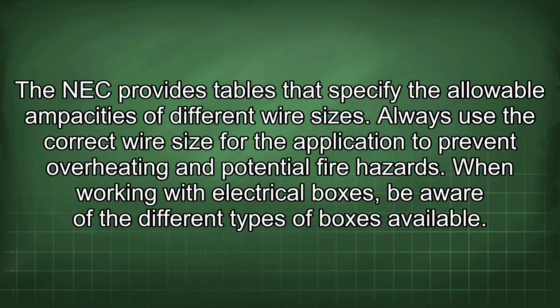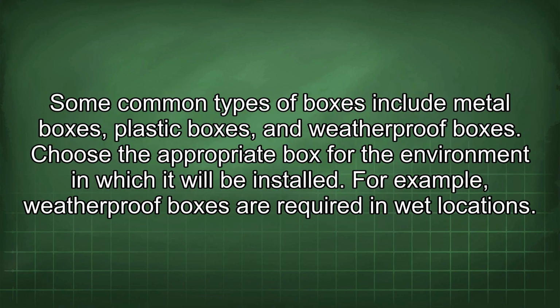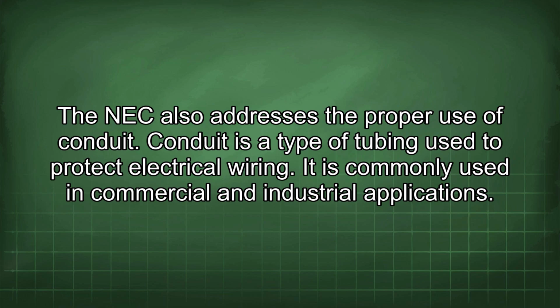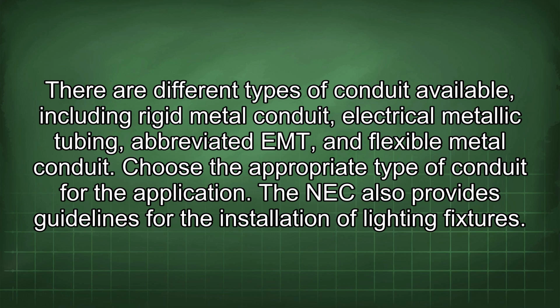When working with electrical boxes, be aware of the different types of boxes available. Some common types of boxes include metal boxes, plastic boxes, and weatherproof boxes. Choose the appropriate box for the environment in which it will be installed. For example, weatherproof boxes are required in wet locations. The NEC also addresses the proper use of conduit. Conduit is a type of tubing used to protect electrical wiring. It is commonly used in commercial and industrial applications. There are different types of conduit available, including rigid metal conduit, electrical metallic tubing, abbreviated EMT, and flexible metal conduit. Choose the appropriate type of conduit for the application.